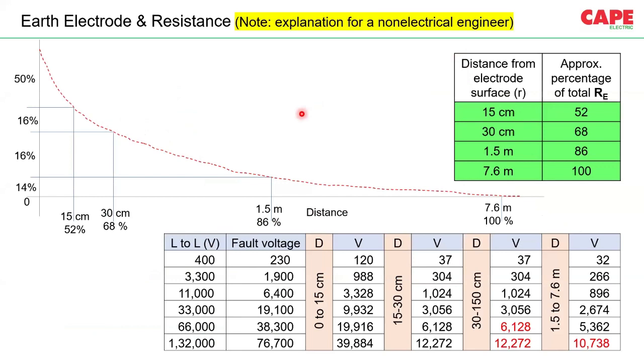Now, I tried to put the same calculation of IEEE 142 for various operating voltages. Say, for example, in a line-to-line 400 volt system, that means in a normal condition, one of the phases creating a fault, the peak of the fault voltage is 230 volt, means in case of a fault of negligible impedance, the exposed conductive part is having a potential of 230 volt. So within a distance of 0 to 15 centimeter, within half a foot, 50% of the voltage has dropped. So that means if you measure the potential from the earth electrode to the next 15 centimeters, you can measure half of the potential. This is for that particular soil. Probably in another soil, it varies.